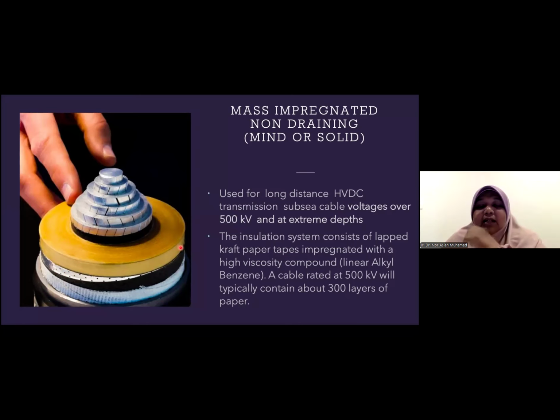So there are environmental effects that need to be considered in order to have a very efficient transmission line. At extreme depth conditions, the insulation system consists of kraft paper impregnated with a high viscosity compound, and the cable is rated normally at very high voltage, which is 500 kV. The paper can be up to 300 layers, depending on the size of the cable.